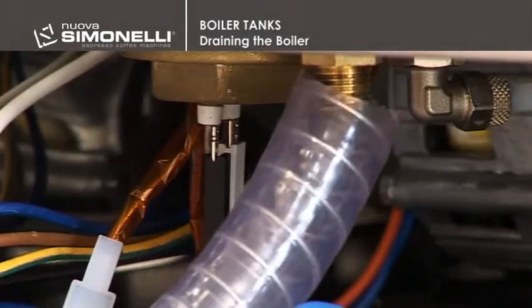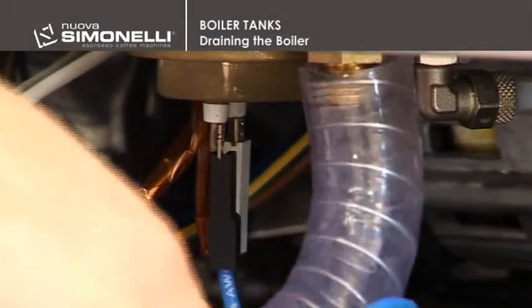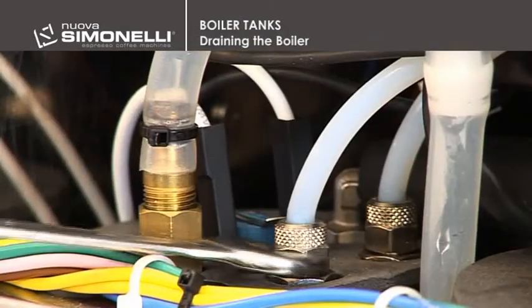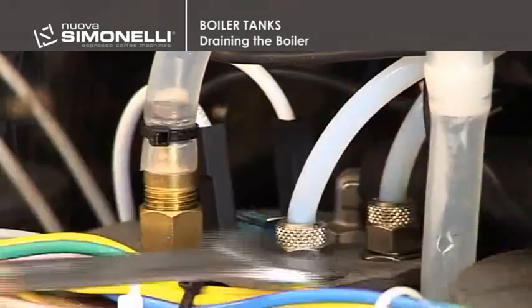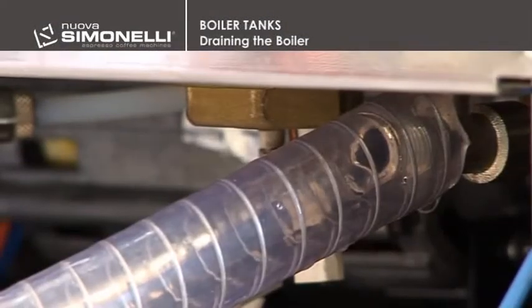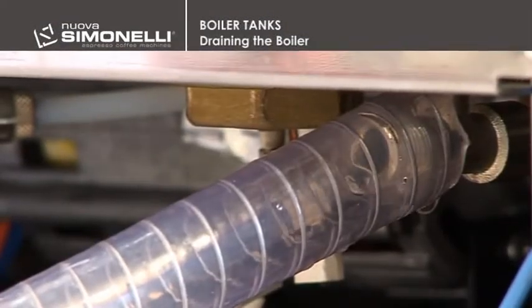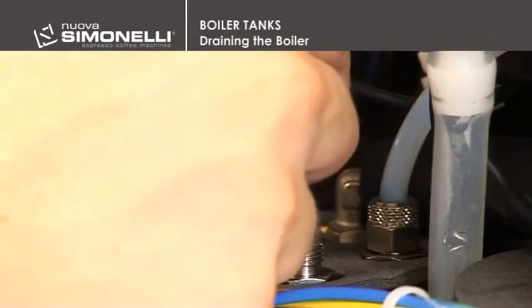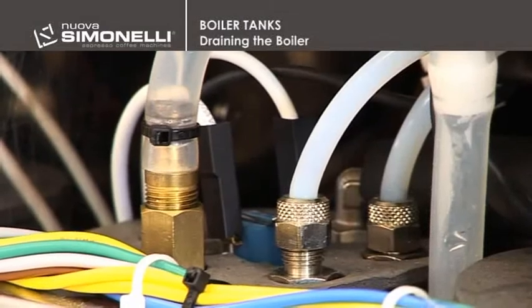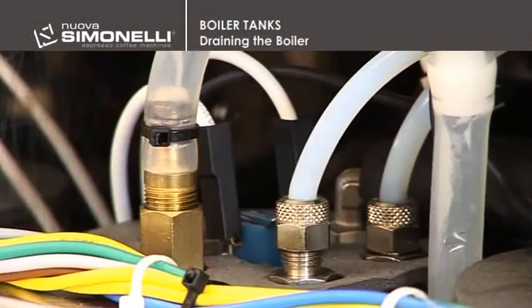Insert a drain pipe and then open a fitting in the top part of the boiler to allow air to enter and therefore water to come out. Wait for the tank to empty completely and then tighten the fitting that was previously opened using a 12 mm wrench before closing the plug again. This procedure is the same for the steam boiler tank.